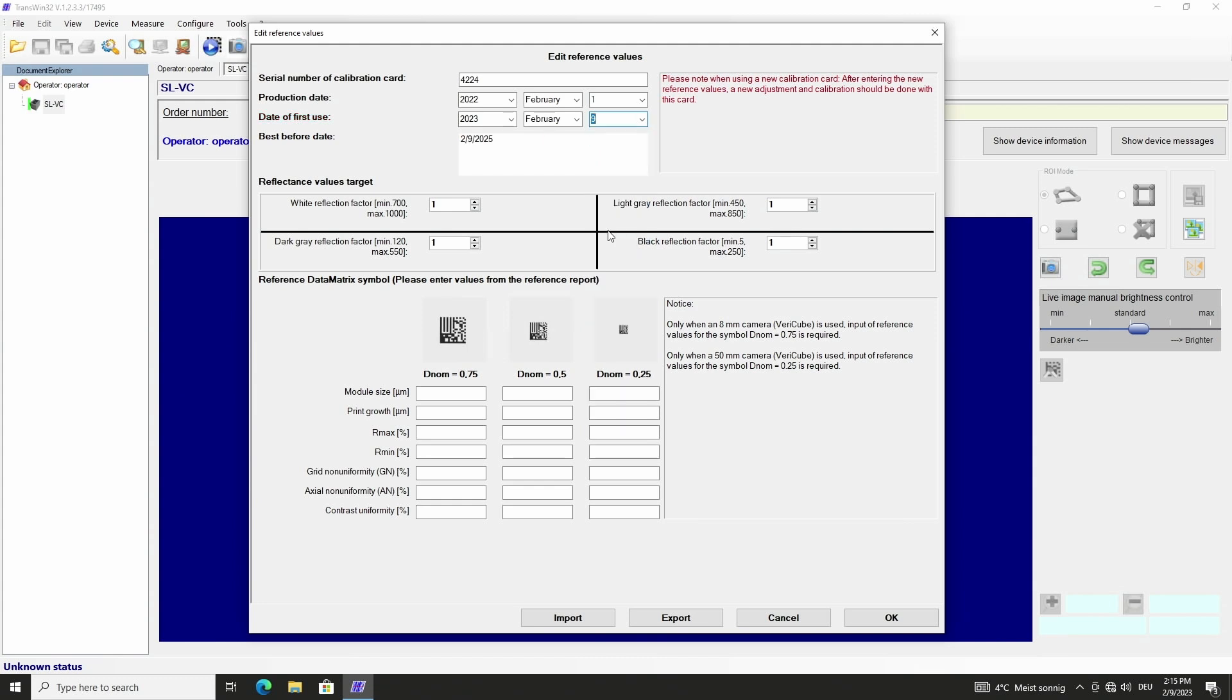The best before date is automatically calculated. It is two years after the day of first use or in maximum four years after production date. After two years in use the calibration cards should be replaced and the new card data must be entered in the software.